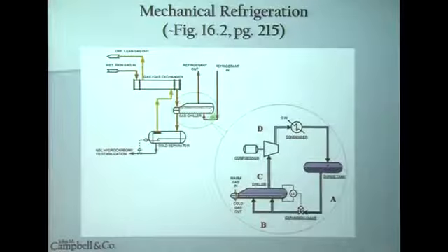to prevent hydrate formation. It goes into a gas chiller where we are boiling propane, and we'll come back to that in a moment. The process gas leaving the gas chiller is at its hydrocarbon dew point specification, goes into a cold separator where we separate the gas and the liquids. The gas then comes out, is cross-exchanged in the gas-to-gas exchanger, and then goes out to the sales gas line.